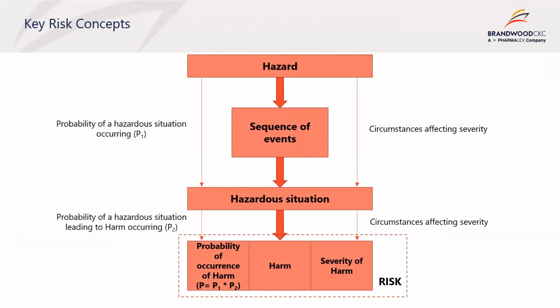Now, to help understand the relationship between the definitions, this diagram illustrates how the manufacturer is to compile a list of known and foreseeable hazards associated with the medical device in both normal and fault conditions, to then consider the foreseeable sequence of events that can produce hazardous situations and harm. According to definitions, a hazard cannot result in harm until such time as a sequence of events or other lead to a hazardous situation. The risk can then be assessed by estimating both severity and probability or likelihood of occurrence of harm that could result. The probability of occurrence of harm can be expressed as a combination of separate probabilities, P1, P2, or as a single probability, P. A decomposition to P1 and P2 is not mandatory, but may be helpful.